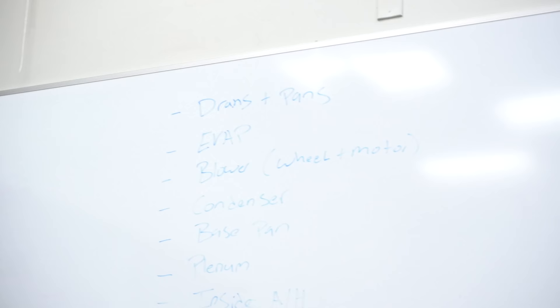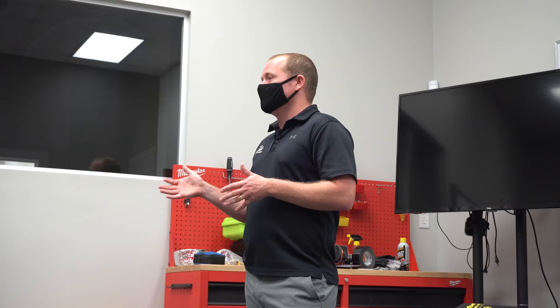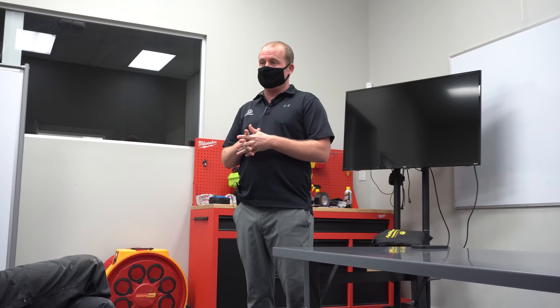When you're doing any sort of cleaning with chemicals — anything where you could get poked in the eye or chemicals could get in your eye, whether brazing, soldering, or whatever — make sure you're wearing your safety glasses. In terms of your drain pan, that's the area that gets missed most often. I want you to have some process of cleaning the drain pan regardless of type — whether it's a case coil, A coil, slant coil, or whatever. You need some method of getting underneath that drain pan and cleaning out those channels.